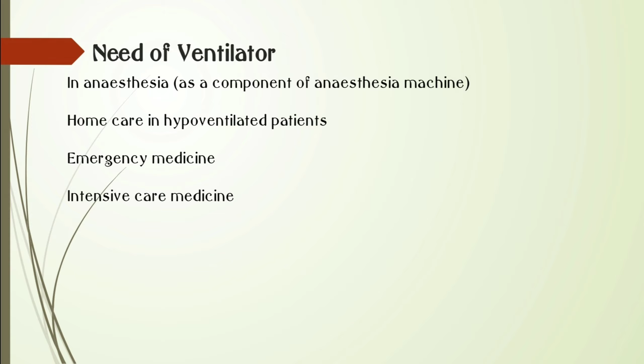Next slide please. Ventilators may also be equipped with monitoring and alarm systems for patient-related parameters, for example pressure, volume and flow, and ventilator functions, for example air leakage, power failure, mechanical failure, backup batteries, oxygen tanks and remote control. The pneumatic system is nowadays often replaced by a computer controlled turbopump. Modern ventilators are electronically controlled by a small embedded system to allow exact adaptation of pressure and flow characteristics to an individual patient's needs. Fine-tuned ventilator settings also serve to make ventilation more tolerable and comfortable for patients.